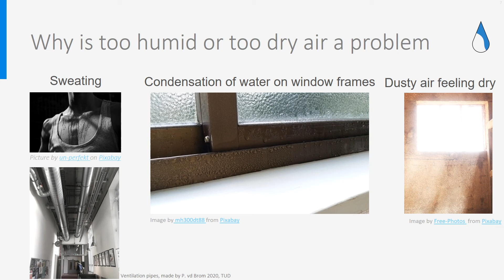The lower limit, at around 30%, has more to do with avoiding electrostatic shocks than with any real burden coming from dry air. In general, when people complain about too dry air, the complaints relate to particulate matter in the air or to a combination of particulate matter, draft and poor lighting causing irritation of eyes or throat. It seldom relates to the low relative humidity itself. Let's say that in general, people experience dusty air as being dry, also when it is not.